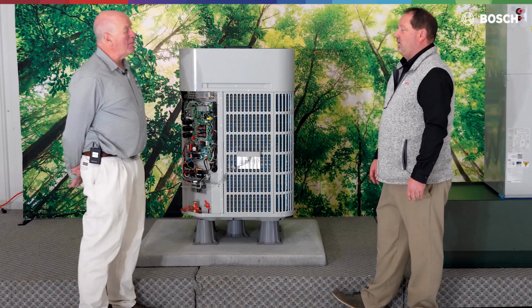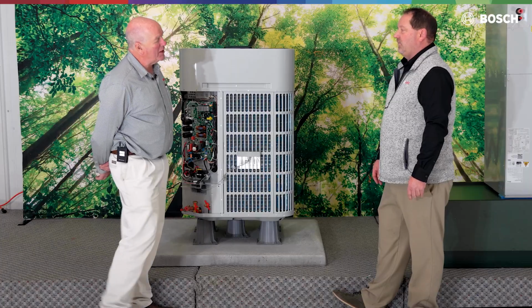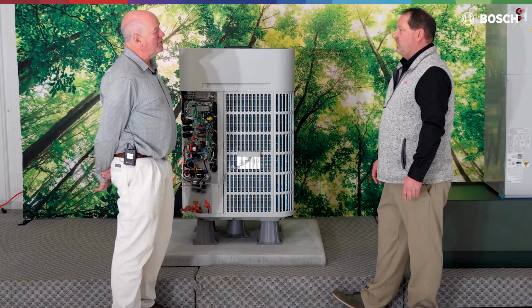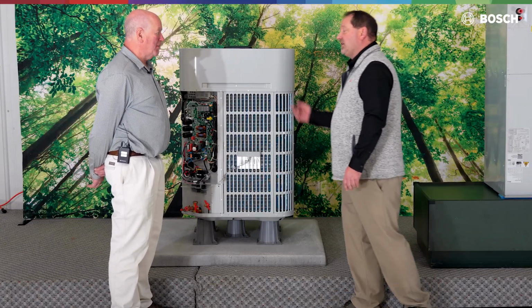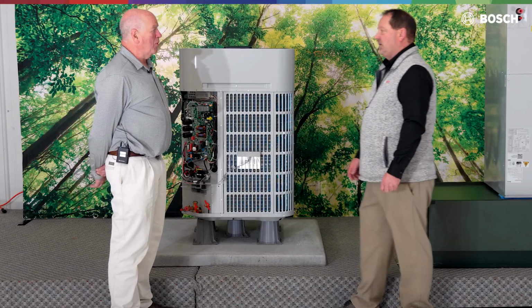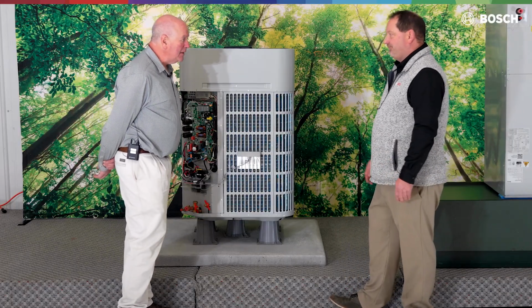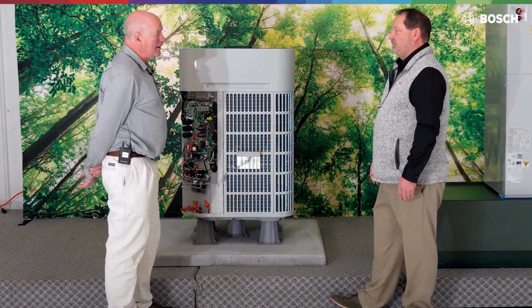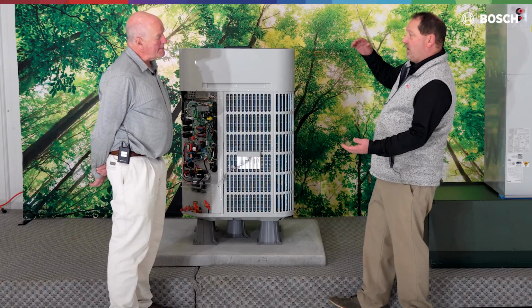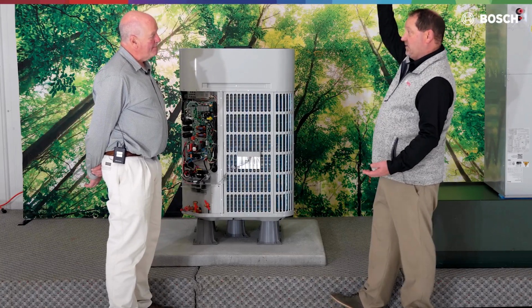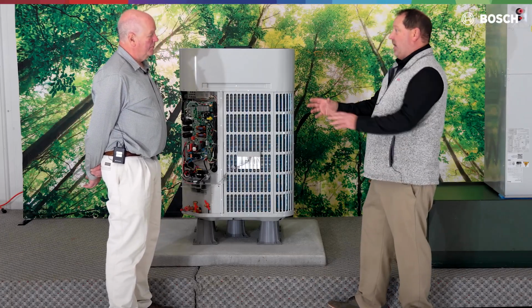We have an oil monitoring package that every 2 hours runs this at near 100% capacity for 5 to 10 minutes to bring the oil back to the compressor. So that's going to bring the oil back. Okay, so that's good. Yep. We already have the crankcase heater built in. We have a pan heater built in. It's all in there. So my evaporator can be on the ground and my condenser on the roof, and vice versa, without oil traps. Correct.